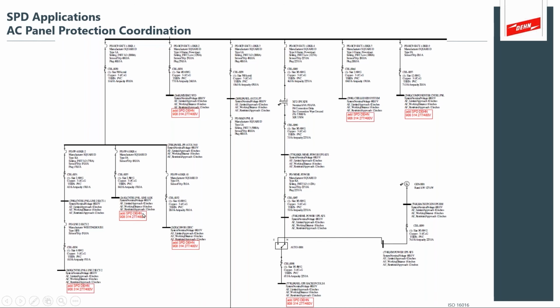And I like to use the term point of use. The closer you get to your very delicate electrical apparatus, the more important it is to have a surge protection device at that point of use, not just at the main service entrance. You want to coordinate that SPD with the point of use. You also want to watch for things like electrical backup generators and transfer switches. And you also have to pay attention to step up and step down transformers, where the transformer introduces a new neutral ground bond. So you need to really pay attention to your bonding and your coordinated surge protection devices.